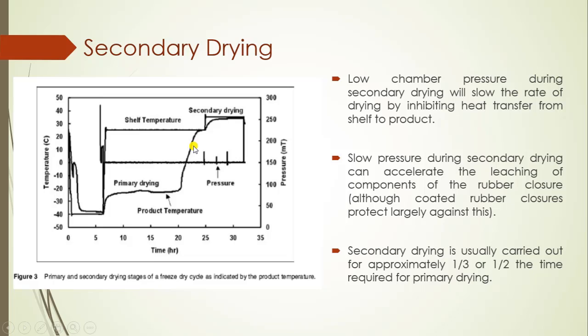The rate of increase in product temperature is quite higher during secondary drying compared to primary drying. Low chamber pressure during secondary drying will slow down the rate of drying by inhibiting heat transfer from the shelf to the product, and low pressure during secondary drying can also accelerate the leaching of components from rubber closures.